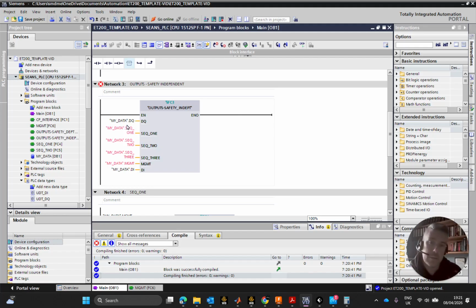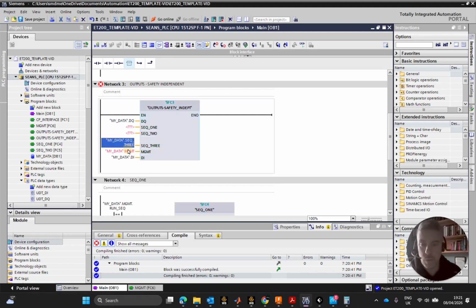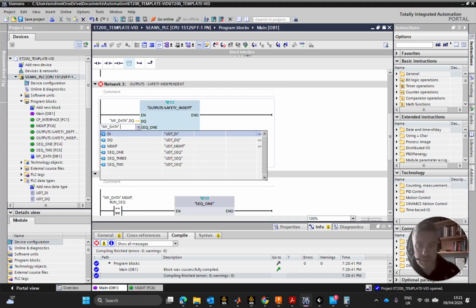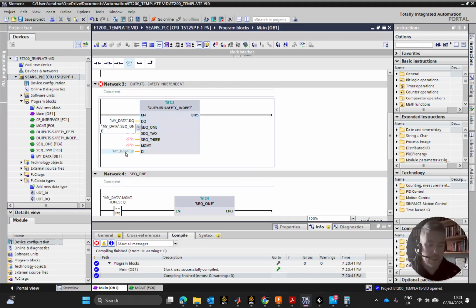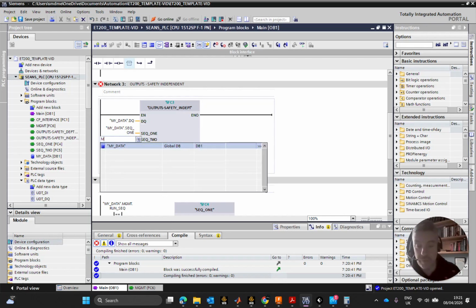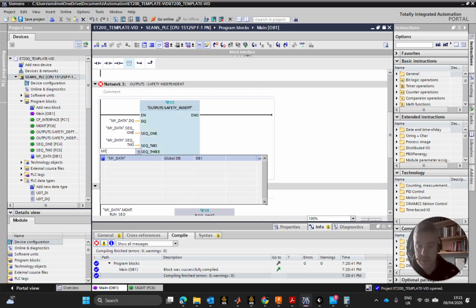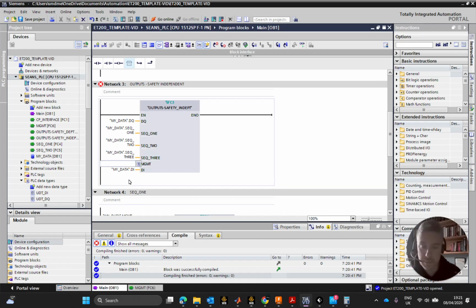I'm not 100% clear on why this happens sometimes when you compile after changing the UDT, and other times it doesn't. Maybe someone might come in and explain it to me. And number two, why it is that they have to be deleted so I can reassociate them, as opposed to them reassociating by the overwritten text entry. But there you have it. Sometimes it's as important, if not more important, to know how to fix these things.